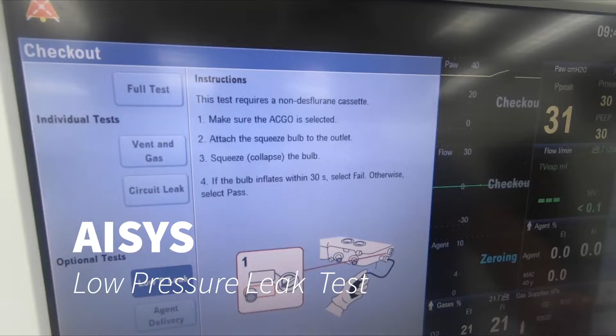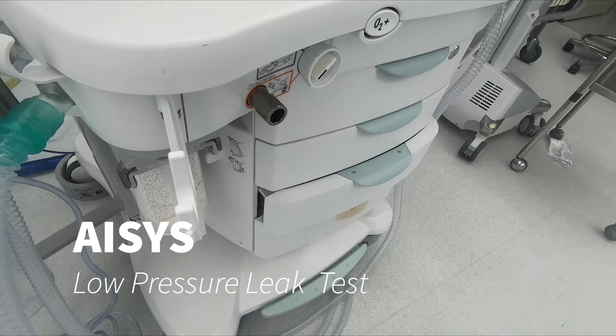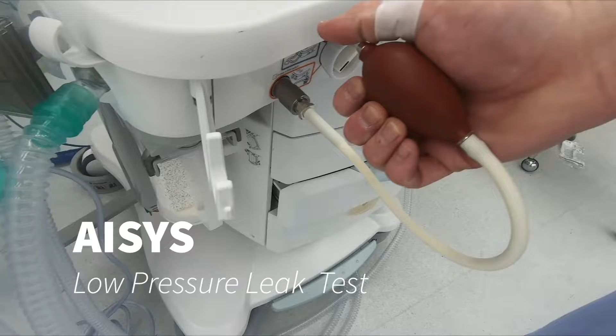Okay, so now we do the low pressure leak test. ACGO selected. So here we're going to switch that on, and the common gas outlet, we have this little bulb system. So step 2, attach squeeze bulb to the outlet. Now we're squeezing the bulb, removing any air and gases from the circuit of the common gas outlet, and so it's flat, and we wait for 30 seconds.